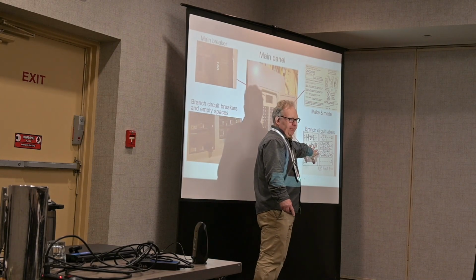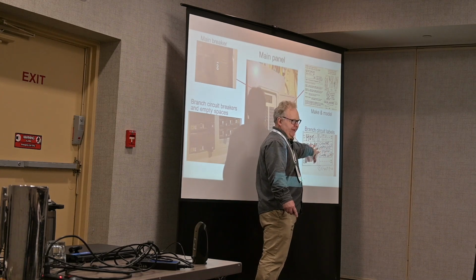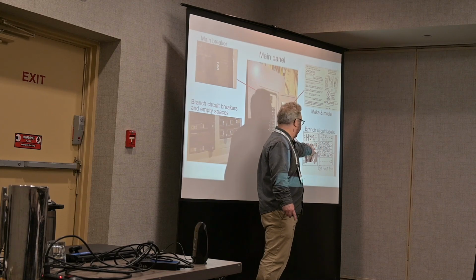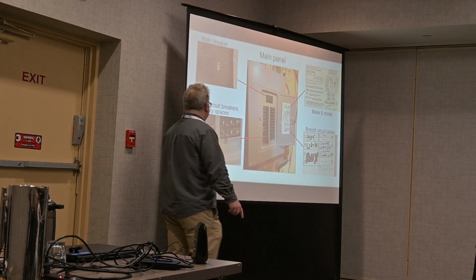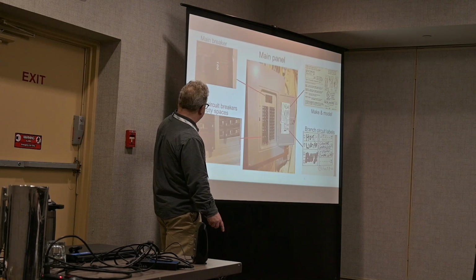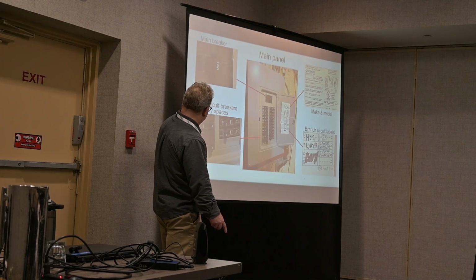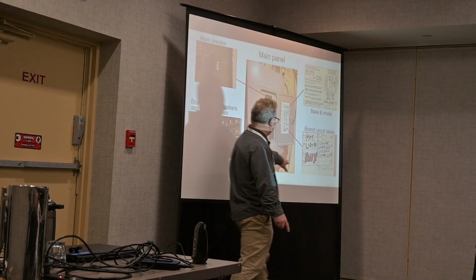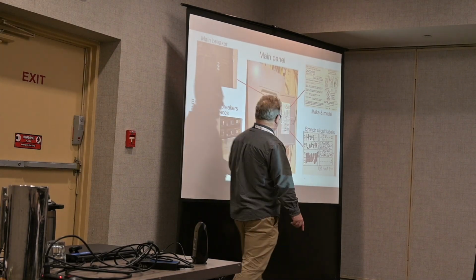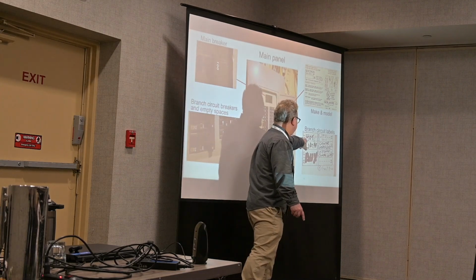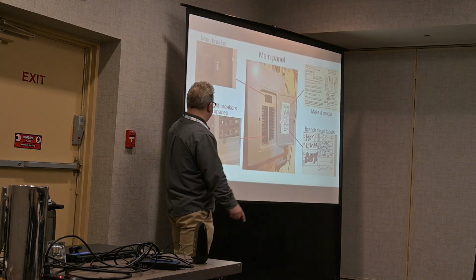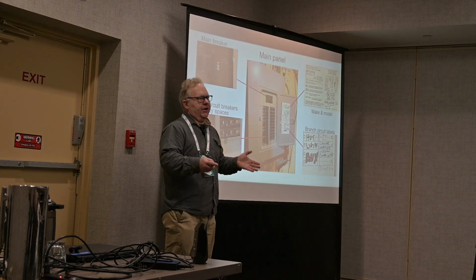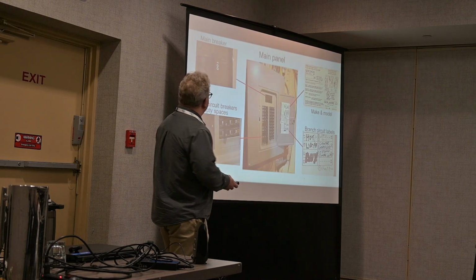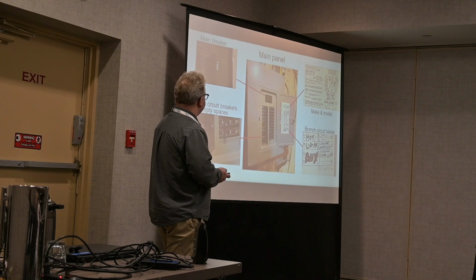The branch circuit labels on an older panel, this is usually a mess. And you can use it in a general way to have some idea what's going on. And then you can actually see what's in there. Okay, I've got a 30 amp breaker that goes with my aux heat for my heat pump. I've got another 30 amp breaker that goes with my water heater. So having good, well lit, high res panel pictures is going to be really helpful.